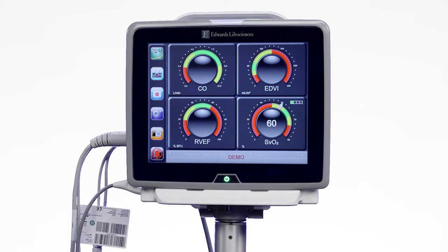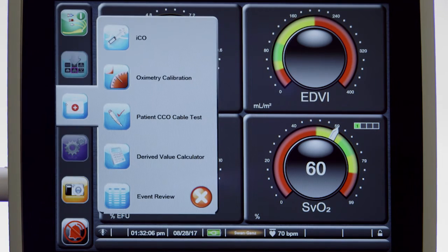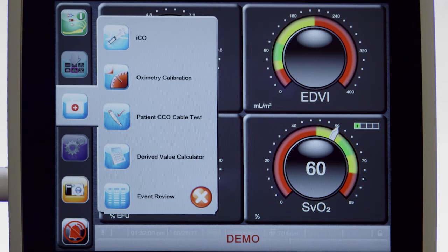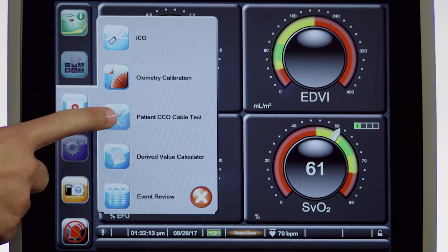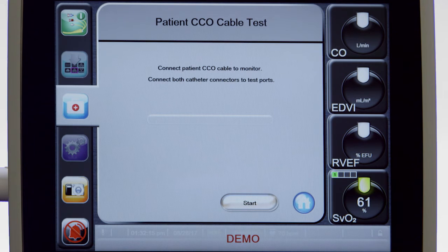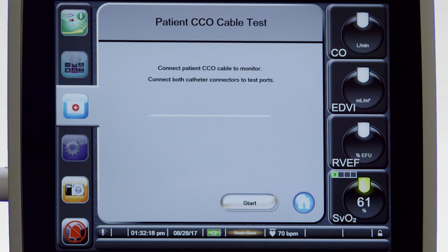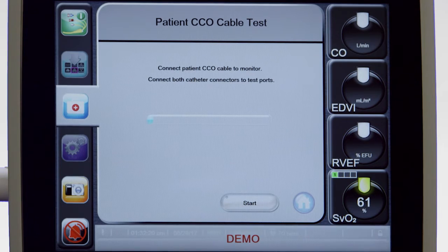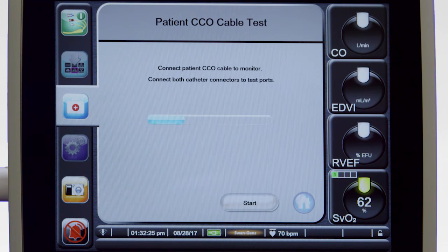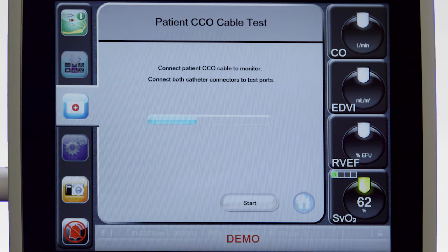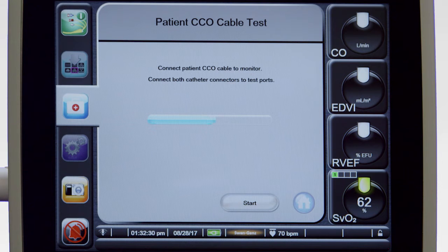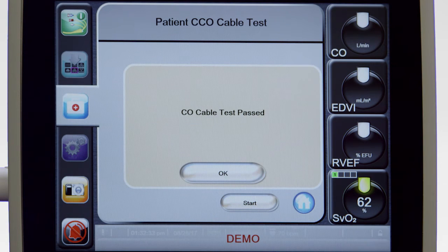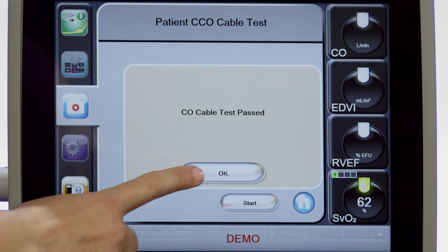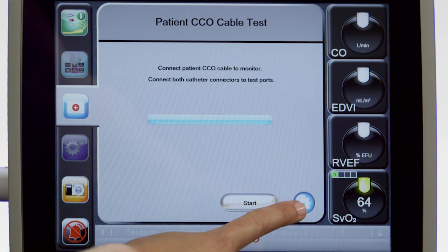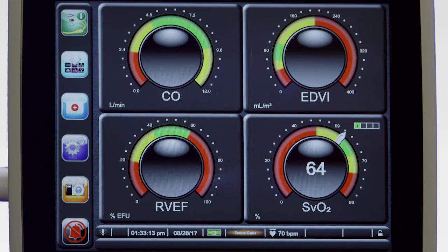Perform a CCO cable test by touching the Clinical Actions icon in the menu bar and then touching the Patient CCO Cable Test button. After ensuring all cables are connected properly, touch the Start button to begin the cable test. A progress bar will appear. If the cable passes the test, it is ready for use. If it fails the test, you should reattempt the cable test, ensuring that all connections are secure, and if necessary, replace the CCO cable and perform the test again. Touch the Home icon when the cable has passed the test to return to the CCO screen.